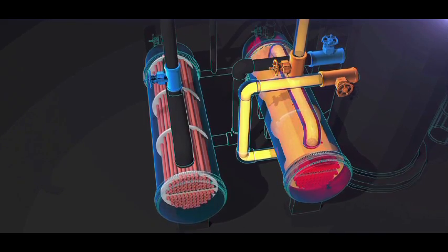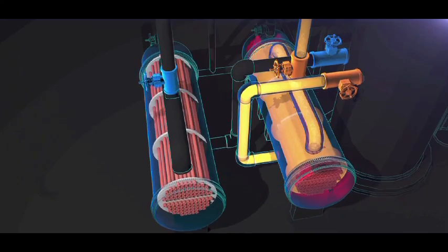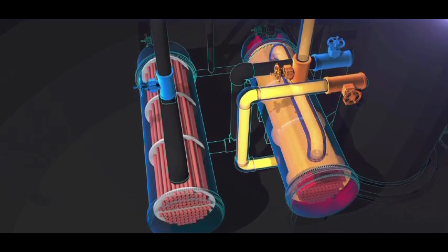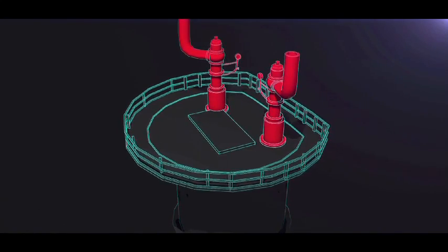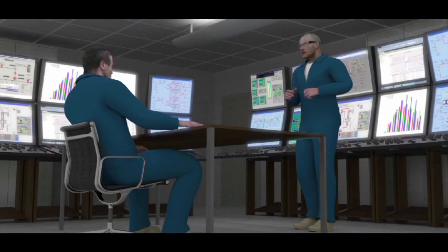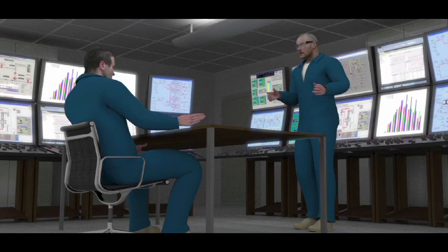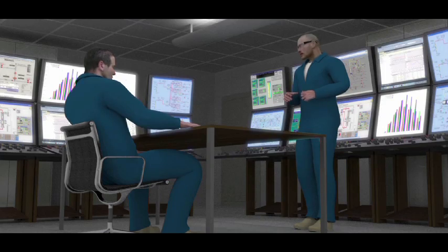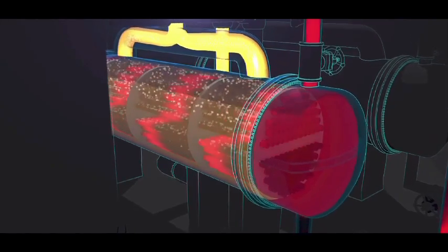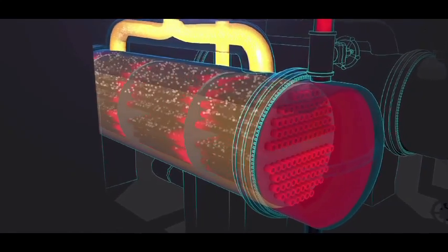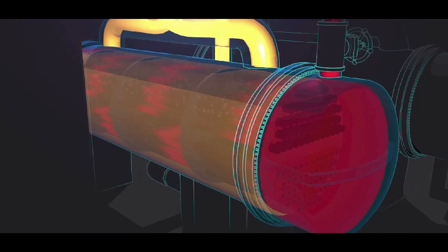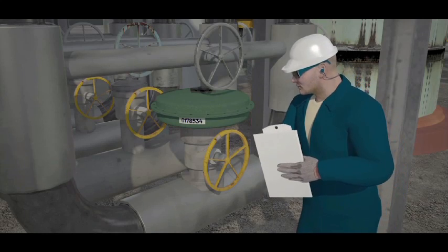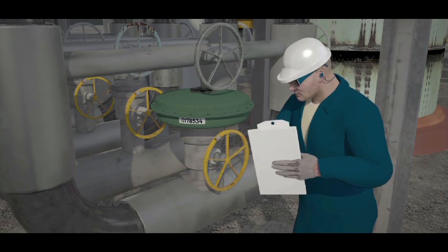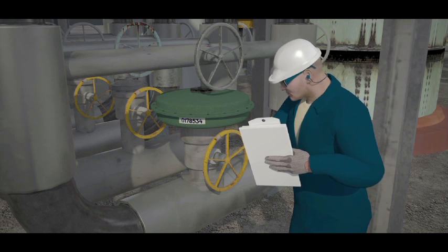But unforeseen at the time, these valves introduced a serious hazard. They isolated the standby reboiler from its protective pressure relief valve, located on top of the fractionator. On June 13, 2013, during a daily meeting with operations and maintenance personnel, the Williams plant manager noticed that the water flow rate through the operating reboiler had dropped gradually over the past day. The operations supervisor informed the group he would try to identify the problem. He went into the plant to evaluate the water flow rates.